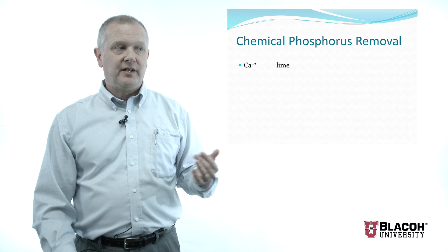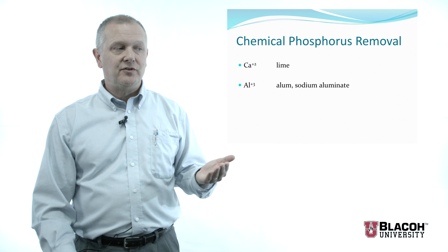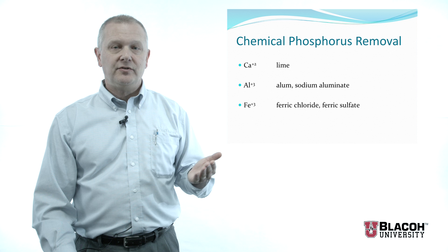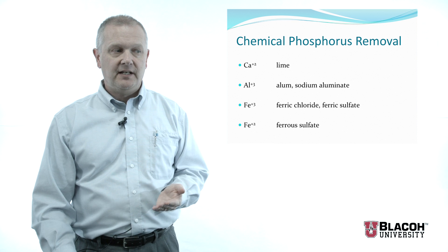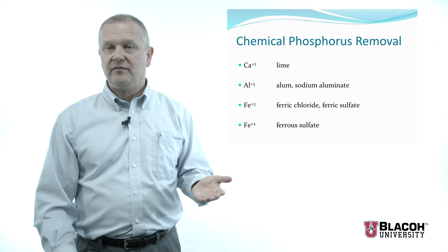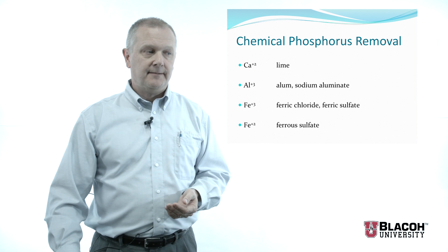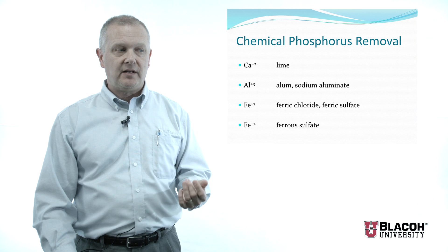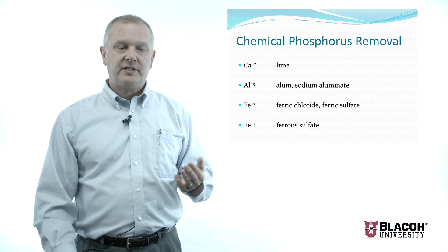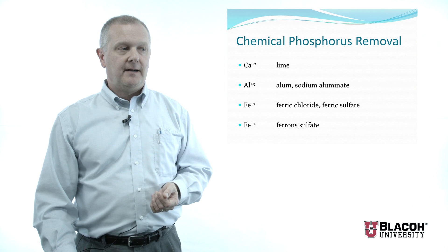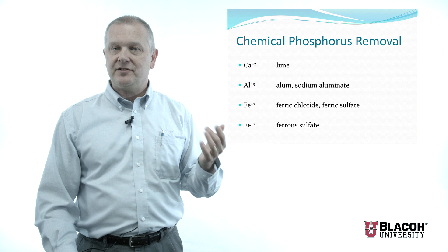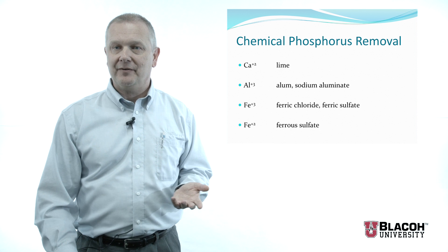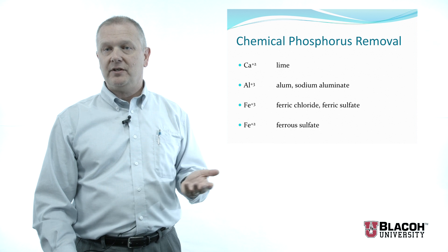These are some of the chemicals that can be used. We can use calcium in the form of lime, aluminum in the form of alum, sodium aluminate, or aluminum chlorohydrate. We can use iron in the form of ferric chloride, ferric sulfate, or ferrous sulfate. Most plants use alum as the least expensive. Some use ferric chloride, which they often use in other parts of the treatment plant. They all have advantages and disadvantages, and each plant has to evaluate what's most cost effective for phosphorus removal.